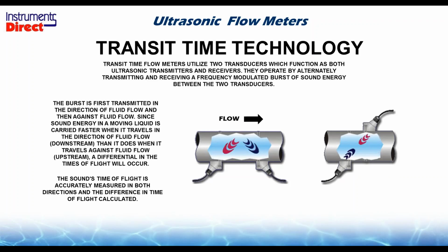say GPM. So we have a couple different configurations on the transit time device here. The picture on the left is what you use most of the time, where both of the sensors are on the same side of the pipe. In this case, we ricochet off the back wall and come down to the sensor here. And we send a sound beam, we ricochet off this back wall and come to the sound beam over here. This type, by different brands, is the dual path or the V configuration you may have heard. And this is the single path or the Z configuration. Those two are most commonly used, and they are associated with pipe size. We're going to get into that a little farther down the road here.